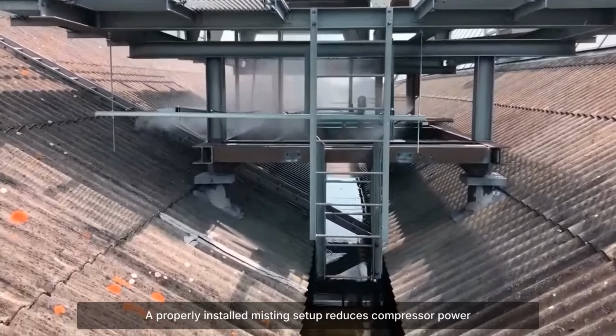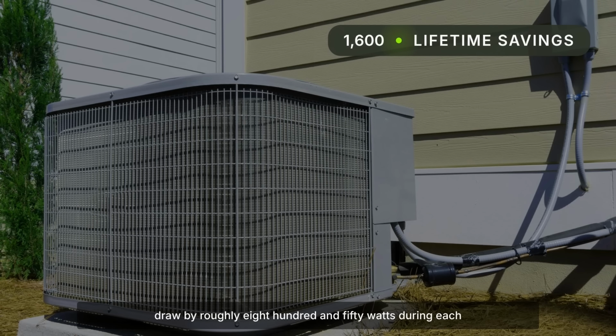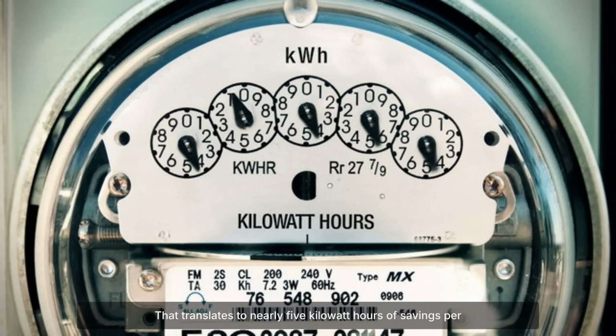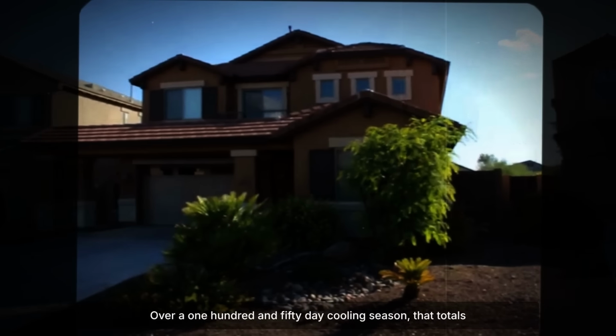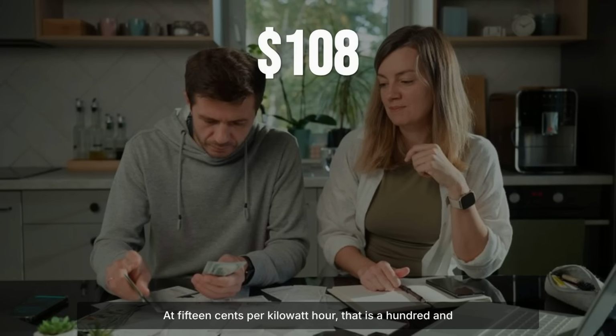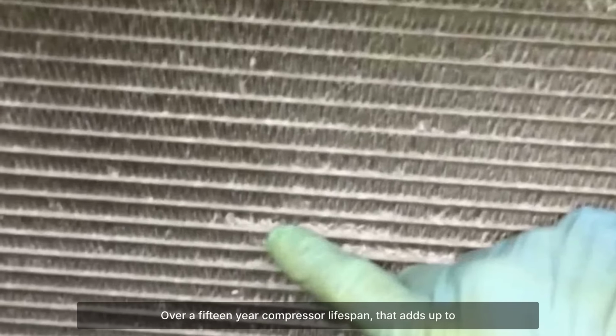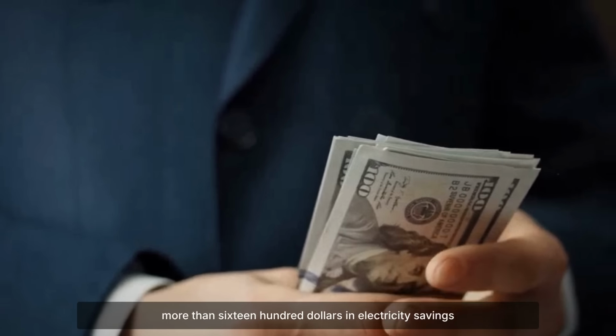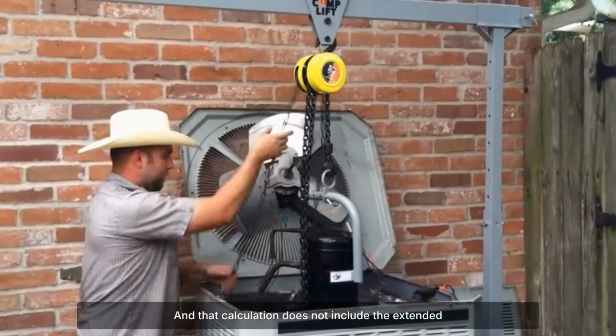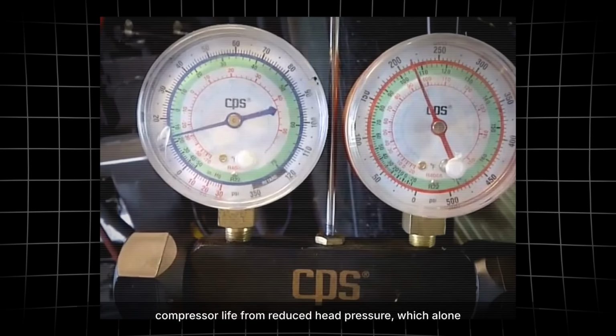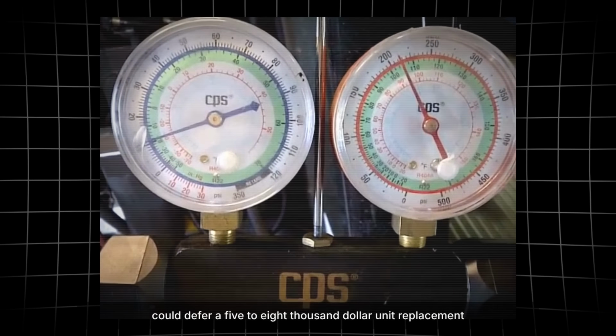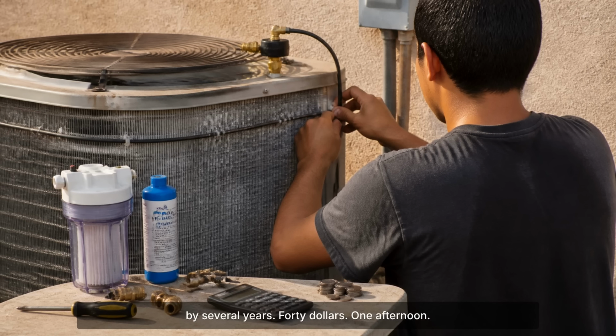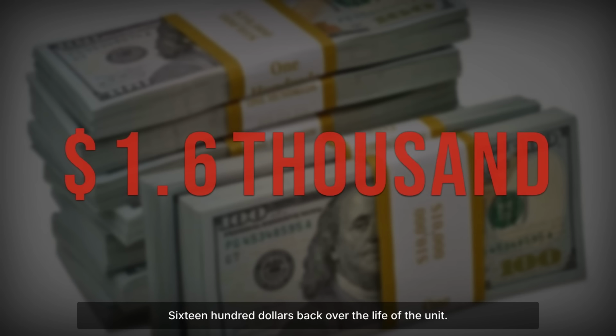A properly installed misting setup reduces compressor power draw by roughly 850 watts during each cooling cycle. That translates to nearly 5 kilowatt hours of savings per day. Over a 150-day cooling season, that totals 720 kilowatt hours saved per year. At 15 cents per kilowatt hour, that is $108 back in your pocket annually. Over a 15-year compressor lifespan, that adds up to more than $1,600 in electricity savings from a $40 investment. And that calculation does not include the extended compressor life from reduced head pressure, which alone could defer a $5,000 to $8,000 unit replacement by several years. $40, one afternoon, $1,600 back over the life of the unit.